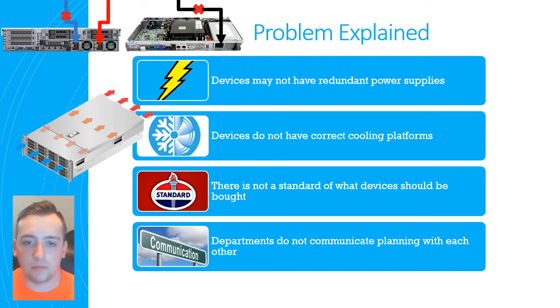If you have equipment that doesn't accept cold air through the front, we'll have difficulty cooling it, because our rows in the data center are set up to provide cool air to the front of the equipment. If instead it wants cool air on the back or side, it can be very difficult to provide that cold air.